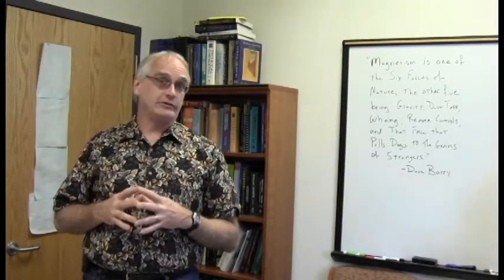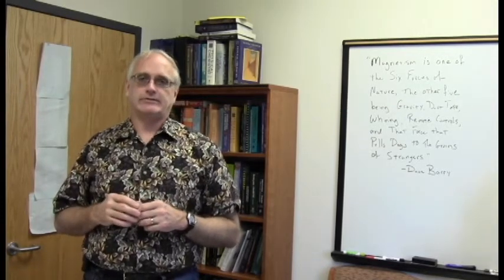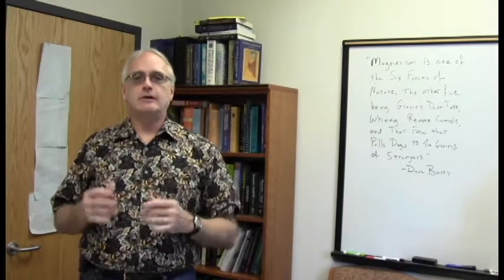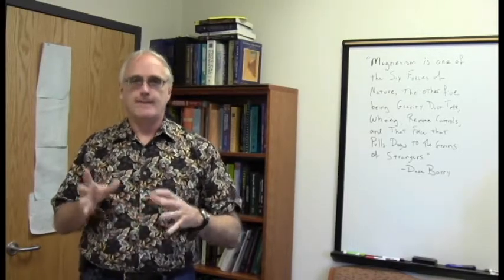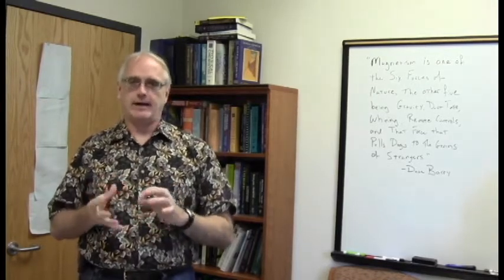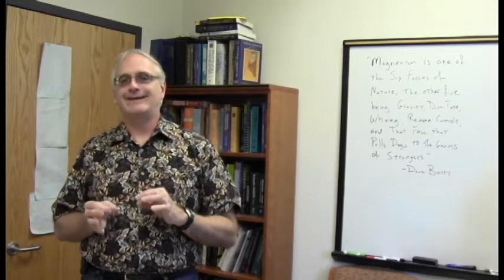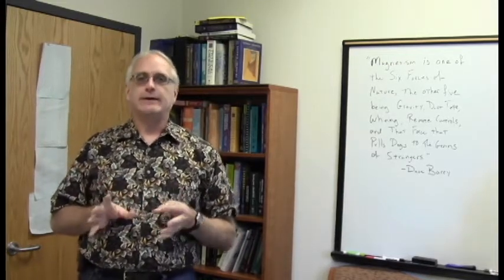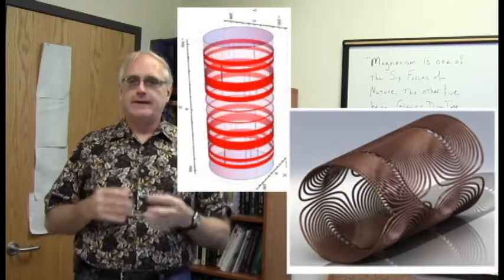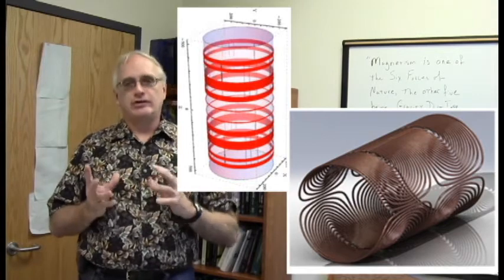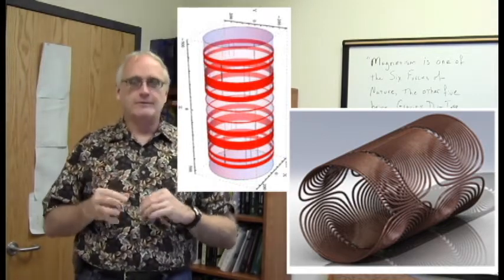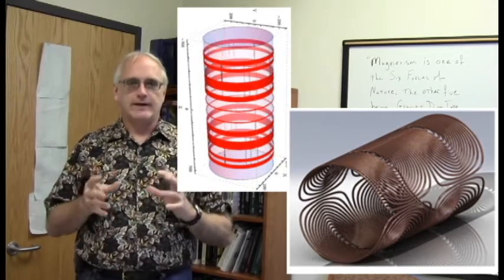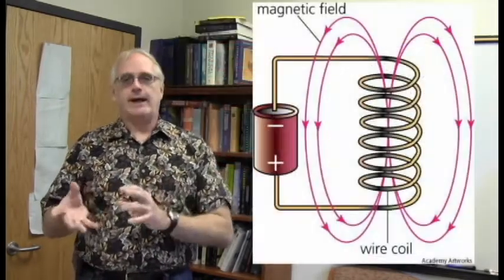In order to guarantee a homogeneous magnetic field along the z-axis, in addition to the big honking magnetic field, we have a set of what are called shim coils. These generate their own magnetic field — much, much smaller than the main field — but they modify B-naught slightly, either adding a bit to it or subtracting a bit from it. They're not uniform or linear; they have various shapes, each with a unique pattern generating magnetic fields that are slightly different on the top or bottom, or left or right. You use those differences to balance out any imperfections in the big magnetic field.